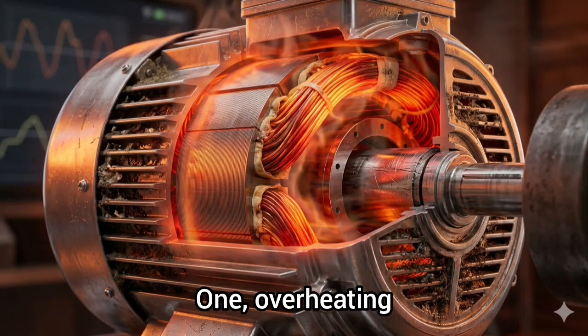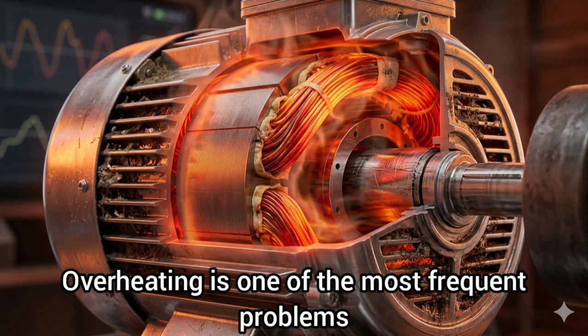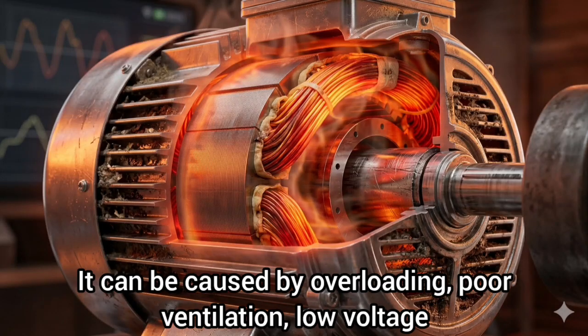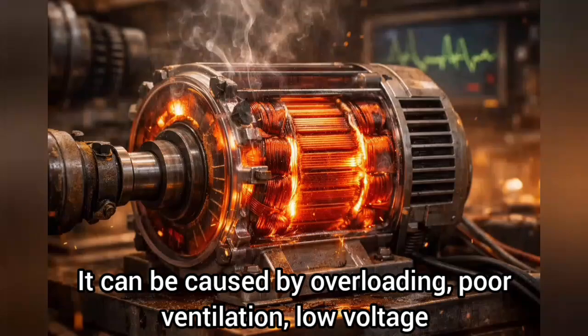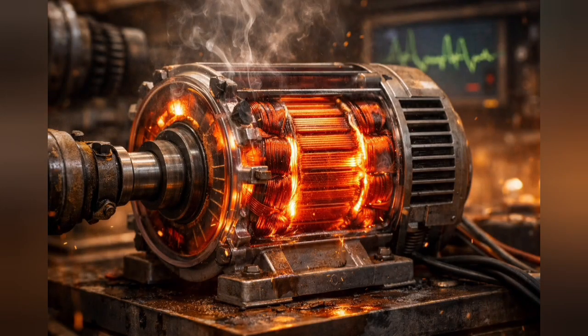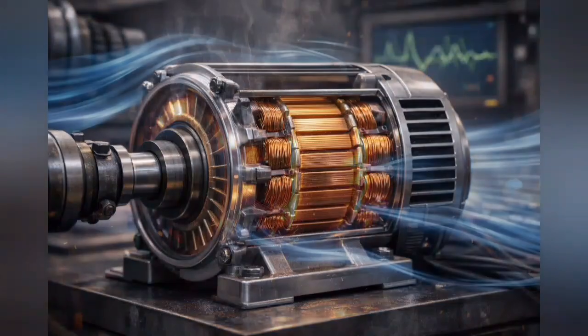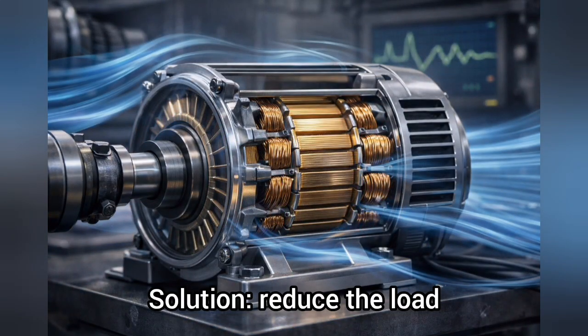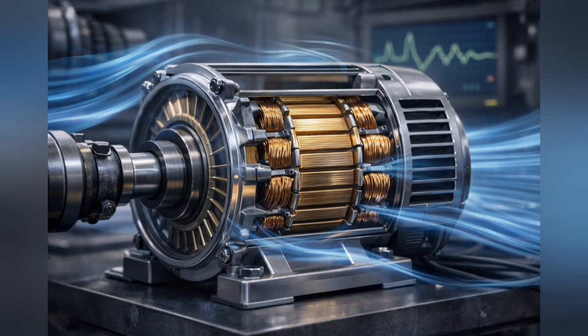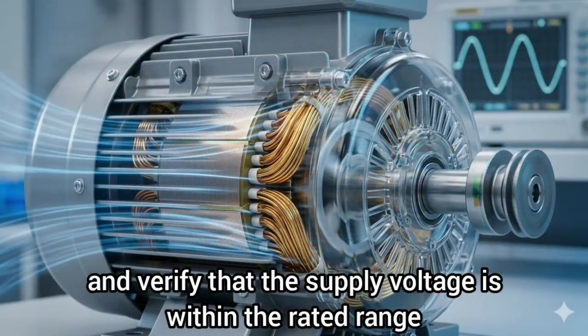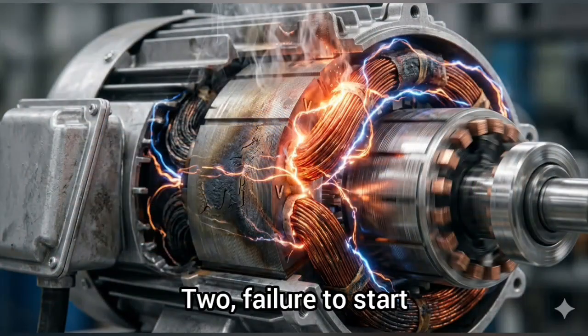1. Overheating. Overheating is one of the most frequent problems. It can be caused by overloading, poor ventilation, low voltage, or high ambient temperature. Solution: reduce the load, ensure proper cooling, clean air vents, and verify that the supply voltage is within the rated range.